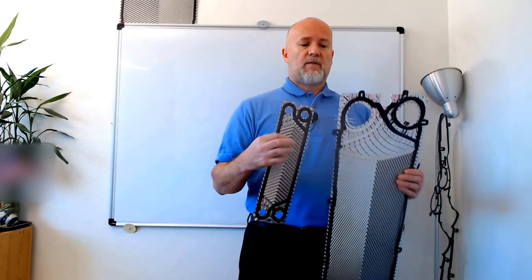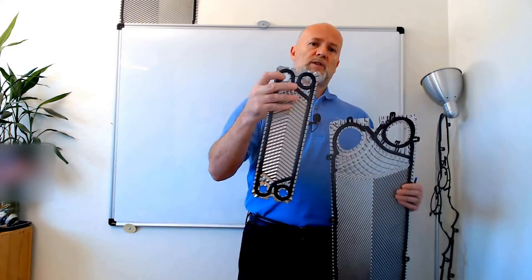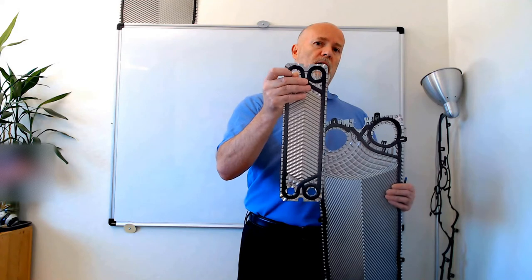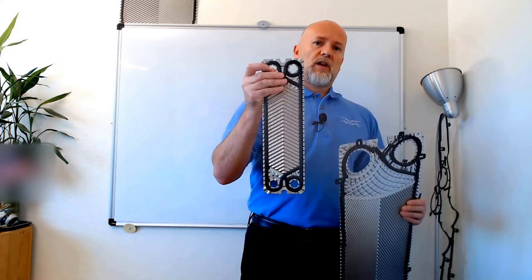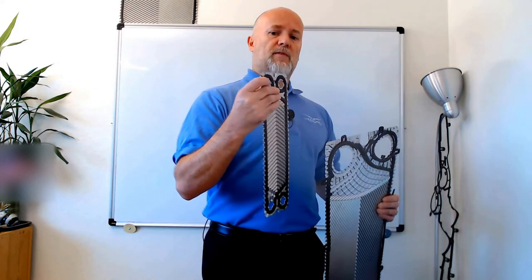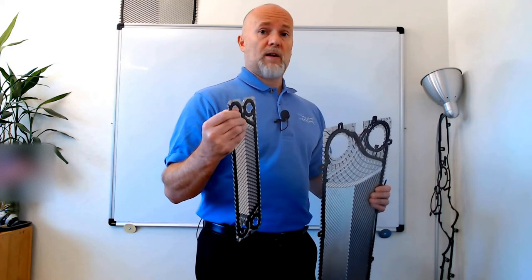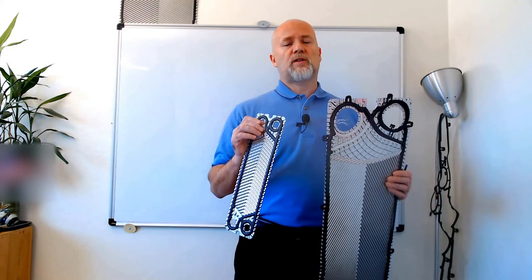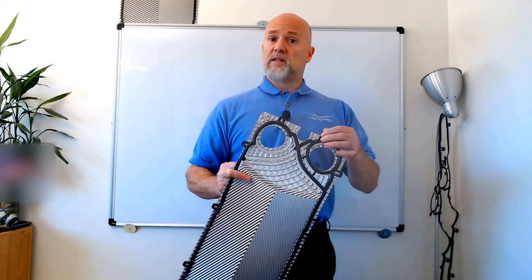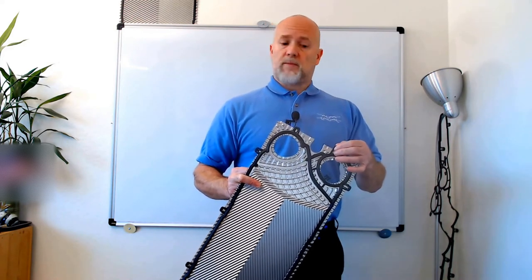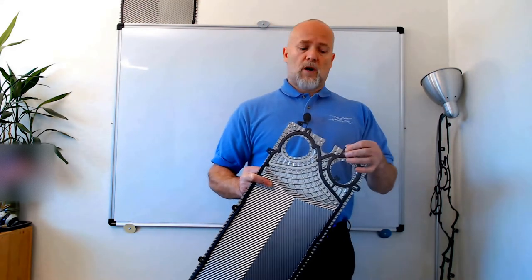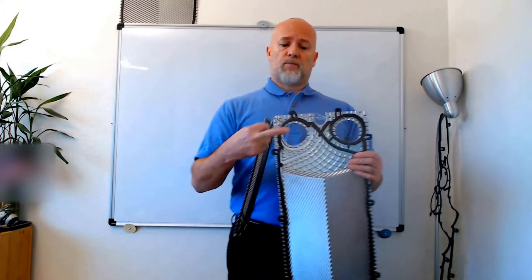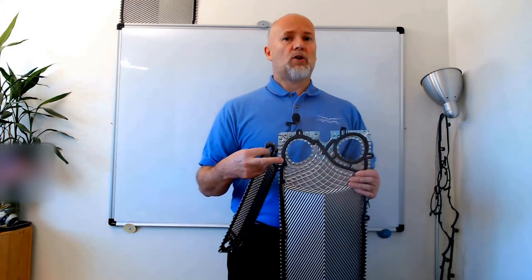But if you have a three inch pipe and you have to squeeze it down into a one inch connection, even though the heat exchanger is cheaper, you have a significant pressure loss at the ports which you really don't want. So watch the size of the connections when you design something and when you are offered something, because if something is cheaper but has a smaller size connection, it might not be the best possible option.